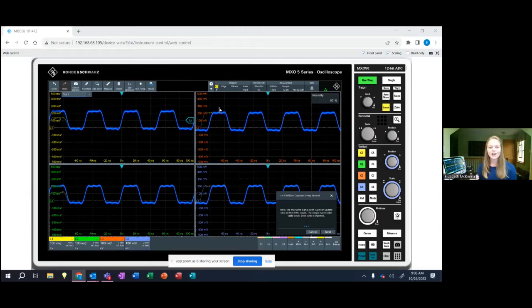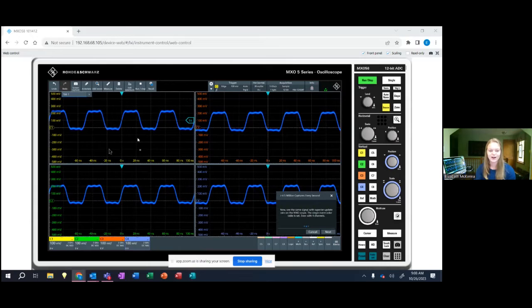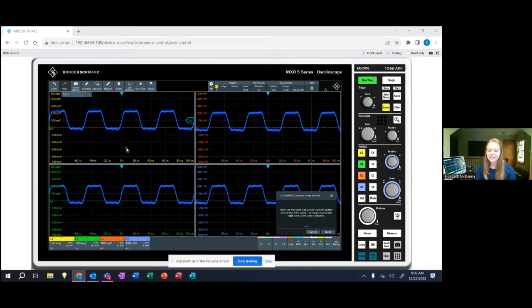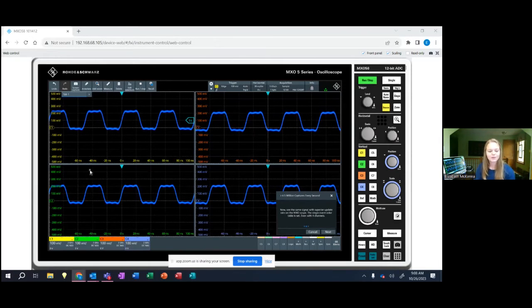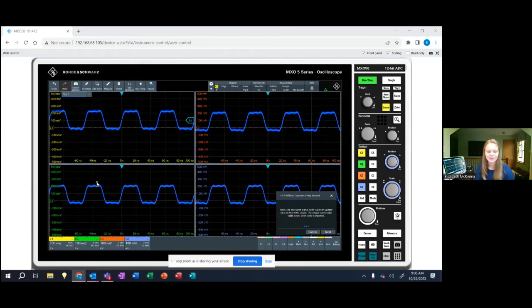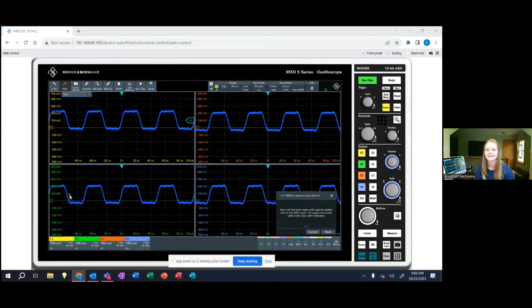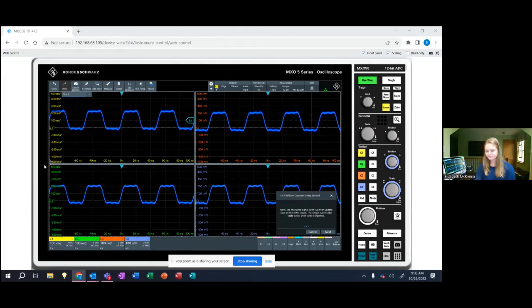With the MXO5 it's got an extremely fast acquisition speed so you're able to update the scope extremely fast and be able to see these rare errors. So as you can see this is the same exact signal that we were showing before but now we've increased the update rate and you can see just how frequently that signal is occurring and the scope is able to capture it.